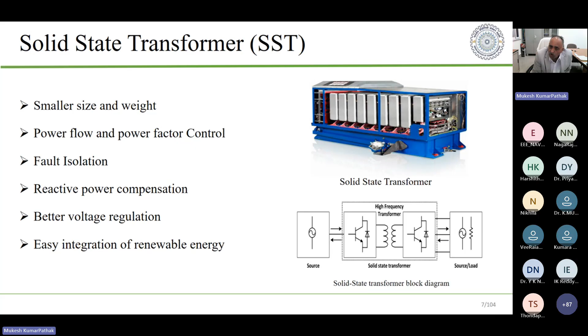And the insulation failure can also be triggered because of higher electrical stresses due to high frequency pulse width modulation waveforms. Now, as I said earlier, this solid state transformer will come with power electronics converters. That means these converters will need pulse width modulations, and these pulse width modulations will cause high voltage stresses across the insulation also. So those stresses can cause failure of insulation.